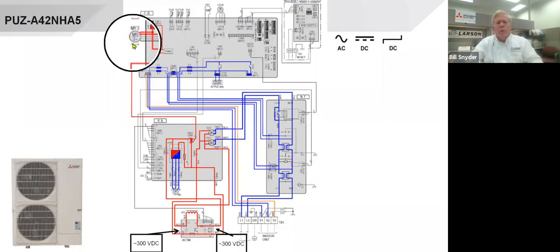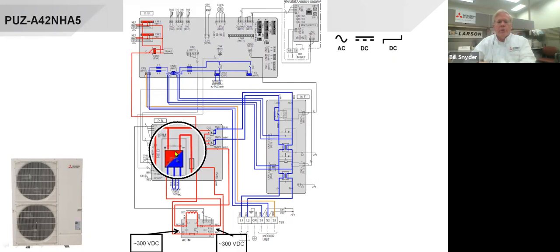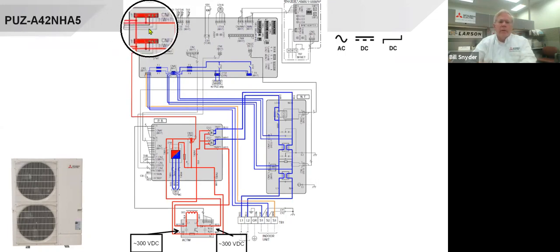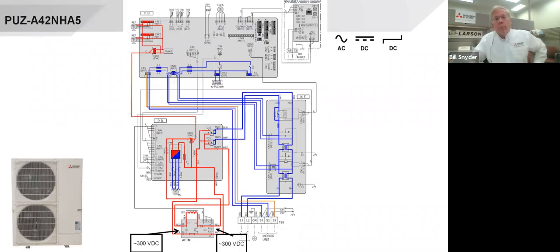What that means is on the motor itself, there's a little circuit board that does this type of conversion. The intelligent power module is built right onto the fan motor. It's inside the fan. If you were to pull the back off the fan motor, you will see a little circuit board with 3 lines coming out of it to the motor that are labeled U, V, and W. Then there's 3 more lines that come out. What we're doing is sending a DC signal to the motor telling it what speed to run at, and then the motor sends a signal back telling the board that it's running at that speed. So it's confirming that the motor is up and running. If the board is telling it to go to so many RPMs and it doesn't get a signal back, it'll send an error code and you will get a phone call to come out and work on the equipment.